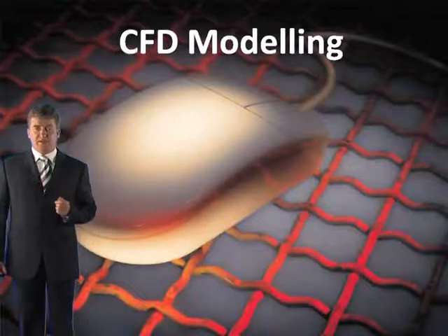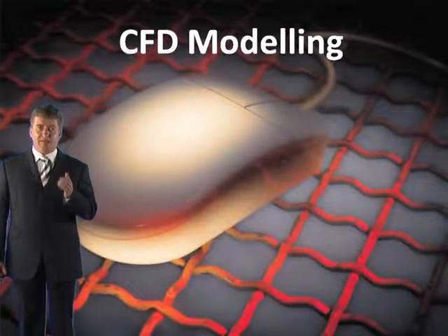Now, an alternative to this is to carry out CFD modelling, or like I said before, you've got your test of the wind tunnel to demonstrate that natural ventilators in this case would still work. So you can do a specific CFD analysis of the particular scenario, and if it's successful, you could argue that mechanical ventilation is not required and you can actually just get away with natural ventilation.